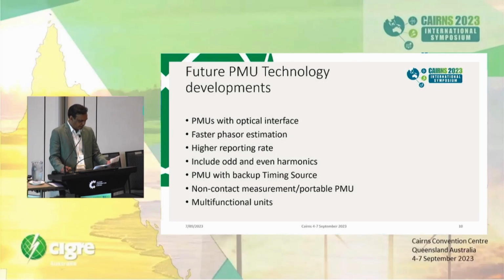Similarly, devices with a high reporting rate will provide more observation points to extend power grid visibility during transients, dynamics, oscillation, first swing, frequency instability, and voltage instability. A high data rate also allows for dynamic response prediction and increases the accuracy of power system model validation.